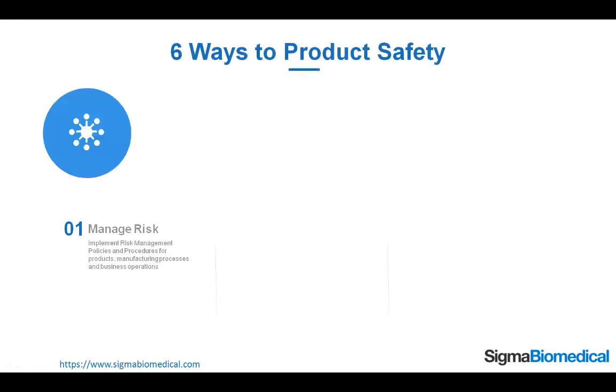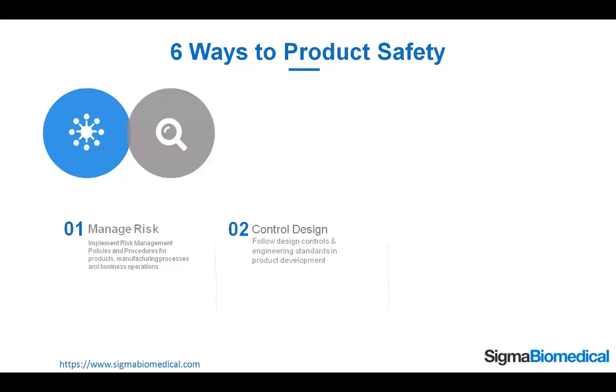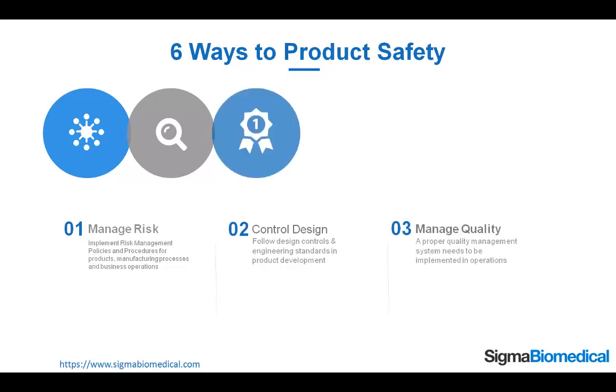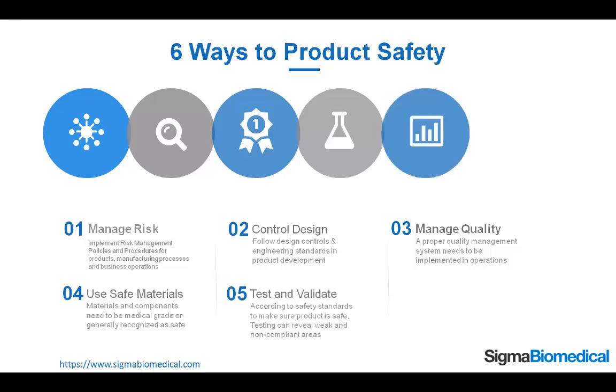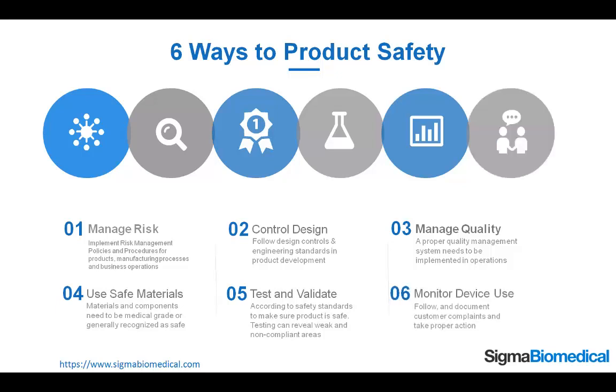Six ways to product safety. 1. Manage risk: implement risk management policies and procedures for products, manufacturing processes, and business operations. 2. Control the design: follow design controls and engineering standards in product development. 3. Manage quality: a proper quality management system needs to be implemented in operations. 4. Use safe materials: materials and components need to be medical grade or generally recognized as safe. 5. Test and validate: according to safety standards, to make sure the product is safe — testing can reveal weak and non-compliant areas. 6. Monitor device use: follow and document customer complaints and take proper action.